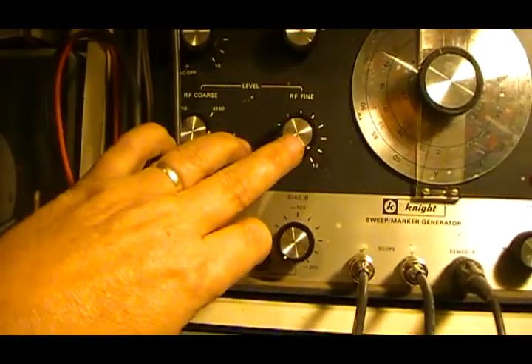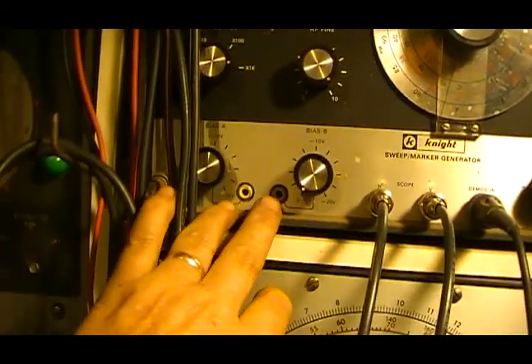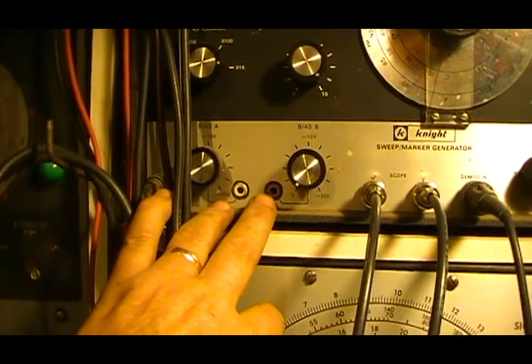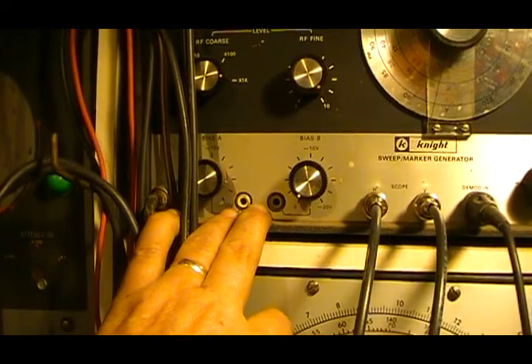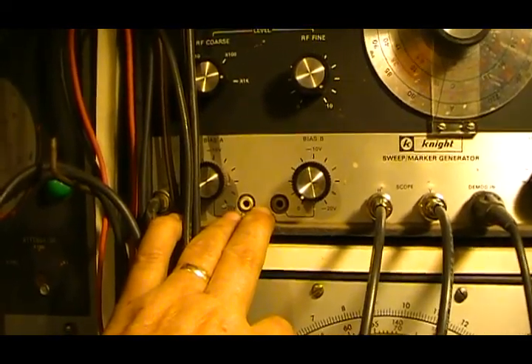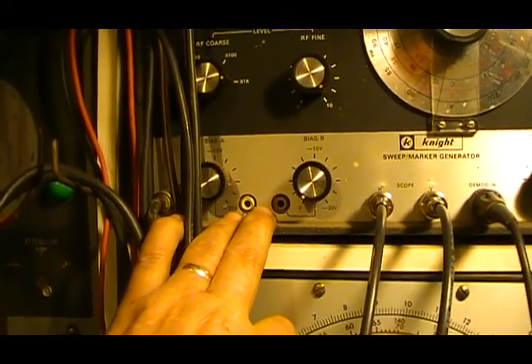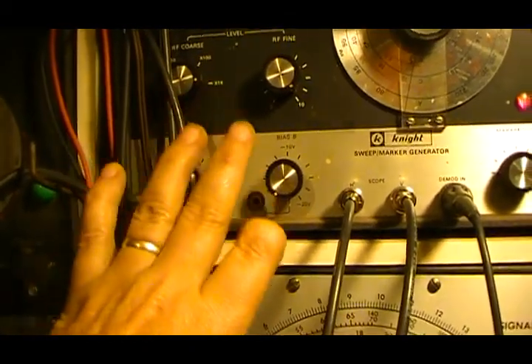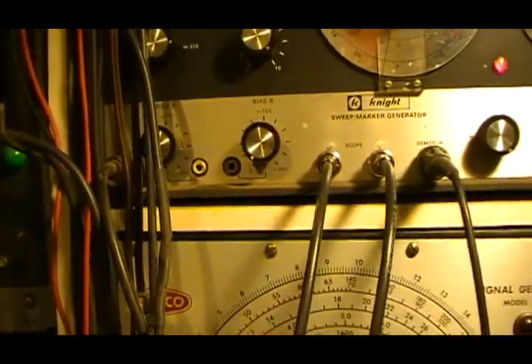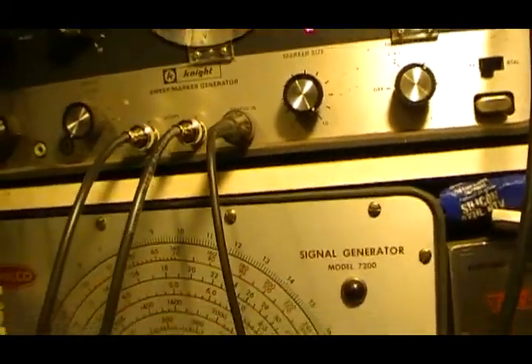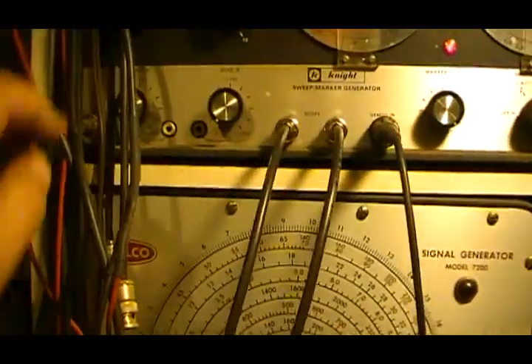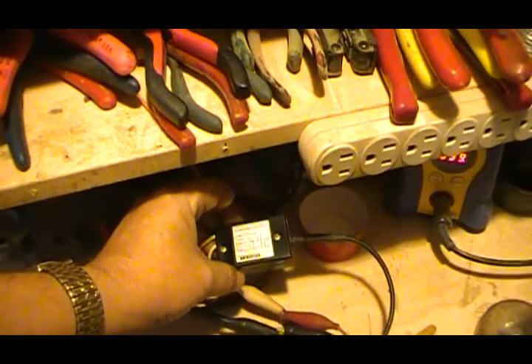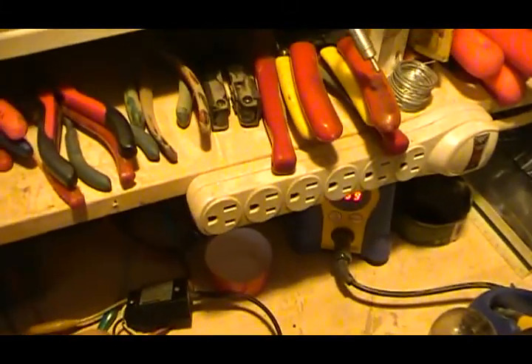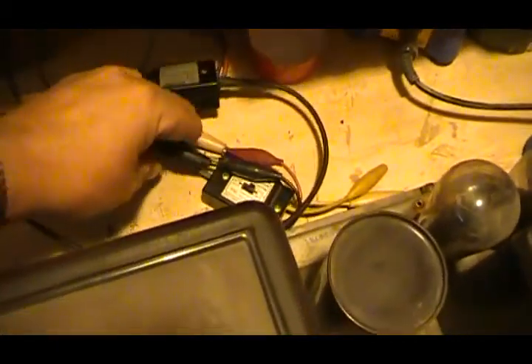And of course, you have your coarse and fine level control, which is your attenuator. This one also has bias voltages that, especially on some TVs, you might want to put in. Generally you put in a bias voltage to shut off the automatic frequency control so it's not fighting you. Both these go up to minus 20 volts, and of course you got the marker size here. For the connections, you got your standard RF. Now this is going to be the input to the radio, and right now we're just tied across to the demod. There's obviously no radio in here, so the two are just connected together.